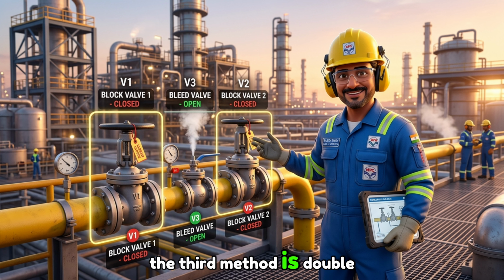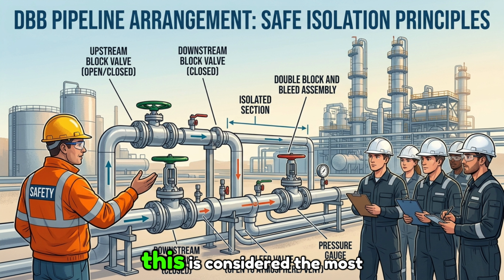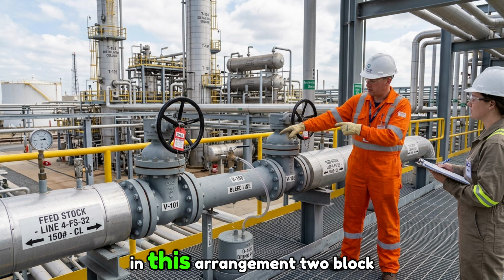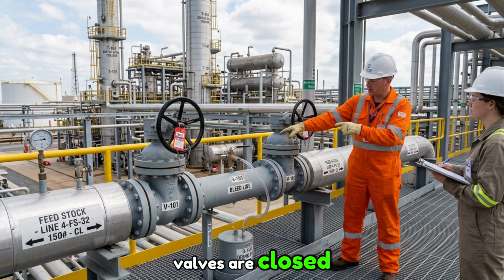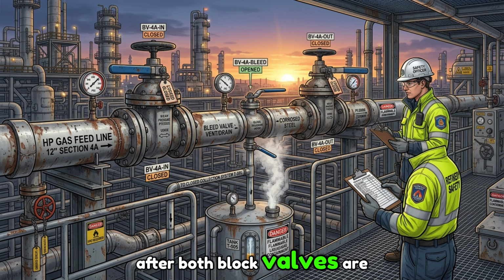The third method is double block and bleed, commonly known as DBB. This is considered the most effective method of primary isolation. In this arrangement, two block valves are closed, and a bleed valve is located between them. After both block valves are closed, the bleed valve is opened to safely release any trapped pressure or process fluid between the two valves.